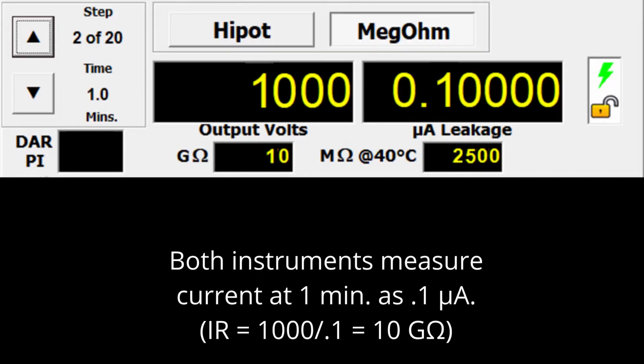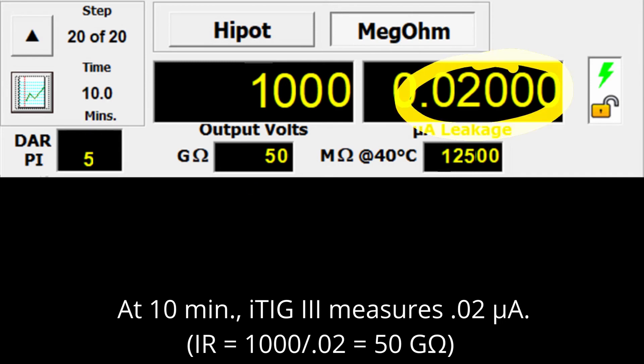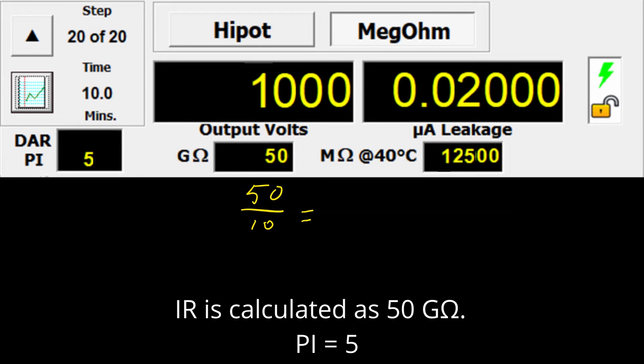Let's say both instruments measure current at 1 minute as 0.1 microamps. And then at 10 minutes, the iTIG III measures 0.02 microamps, well within its range. IR is calculated as 50 gigaohms, and therefore PI equals 5.